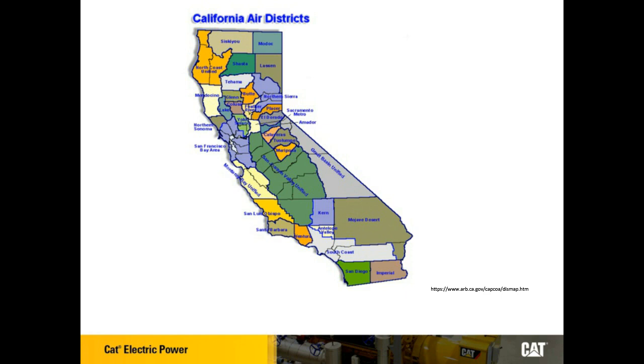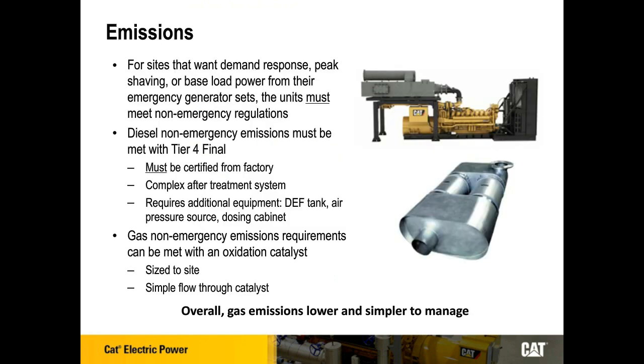We've talked mostly about standby. I want to take a quick moment to talk about the non-emergency product. For sites wanting to do demand response, peak shaving, or base loading for their generator sets, the units must meet these non-emergency emission regulations. As I spoke to earlier, these are the more strict requirements for your NOx, your CO, and your PMs, for both your diesel and gas generator sets.